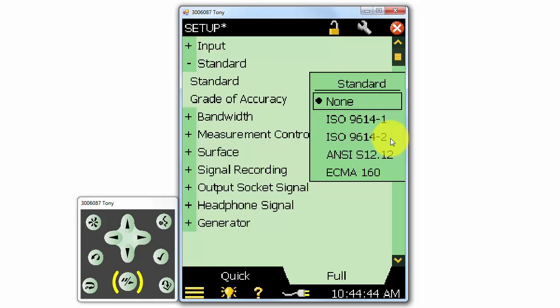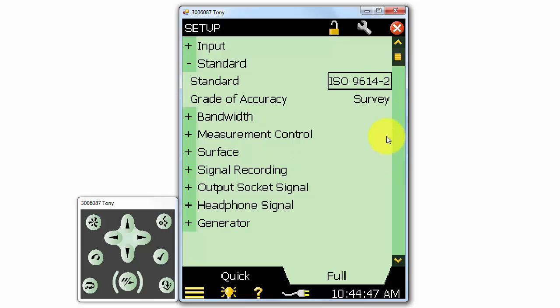For example, if we select ISO standard 9614-2, the ISO scanning method for sound intensity based sound power determination, we'll be required to make two scans of each segment because that is required by the standard to determine the repeatability of the measurement.